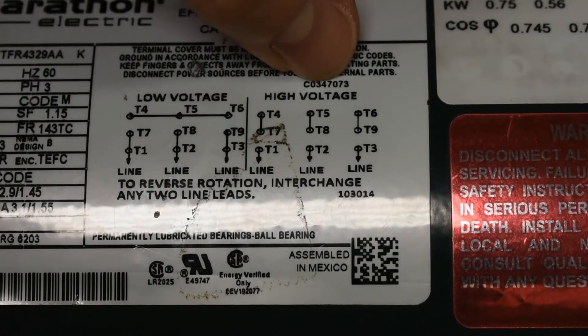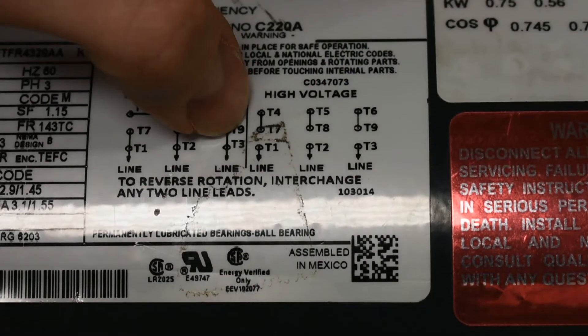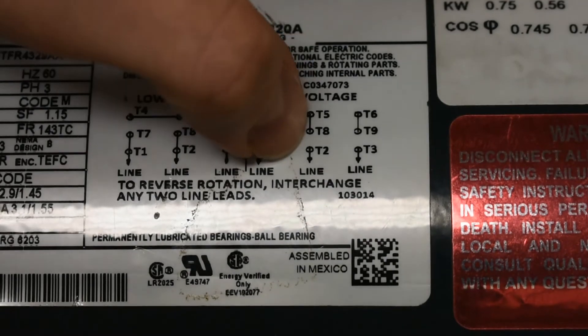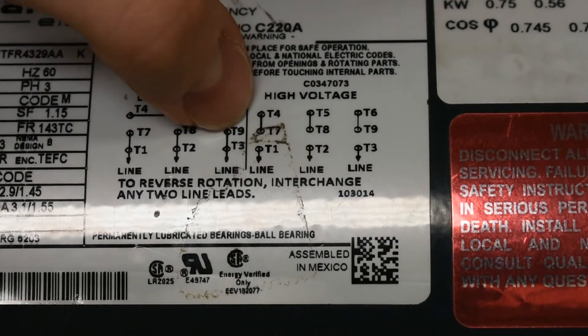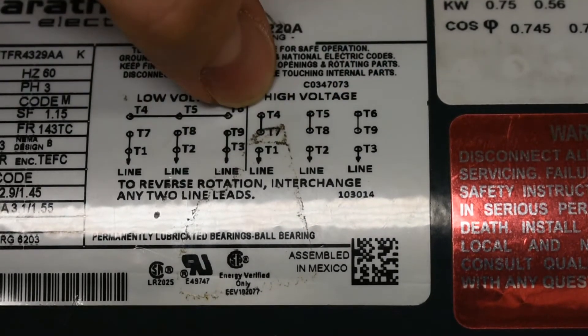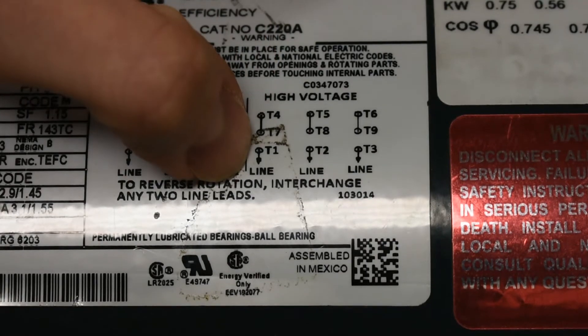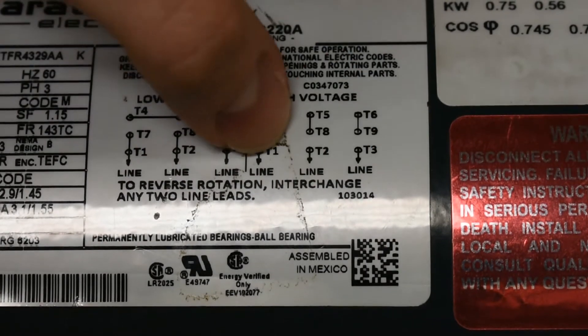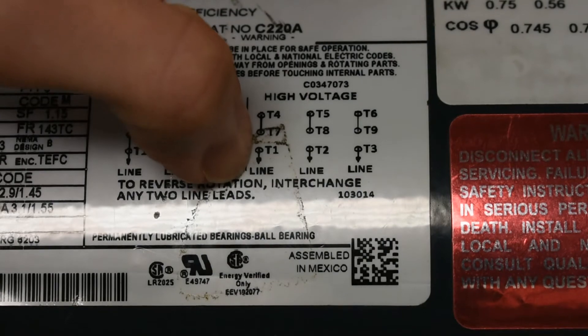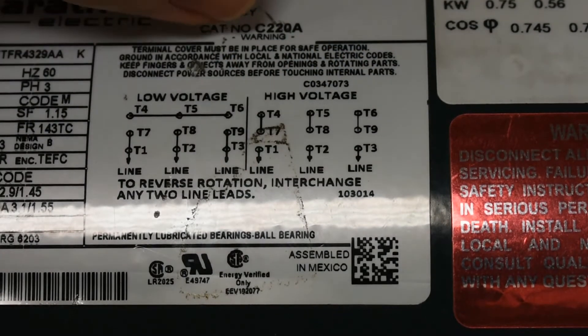Now over here at the high voltage, which means more on the 480 end, we would connect 4 and 7, 5 and 8, 6 and 9. So each one of those sets of wires would have two wires under the wire nut. And then T1, 2, and 3 each going to one of the lines. So again, we're going to have a single wire nut for each one with two wires underneath it.